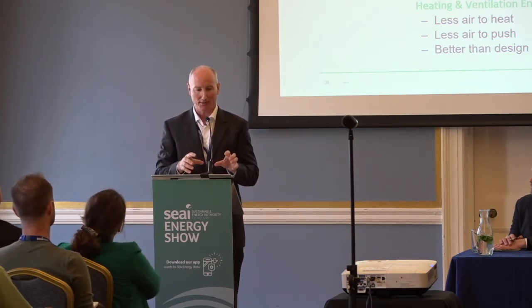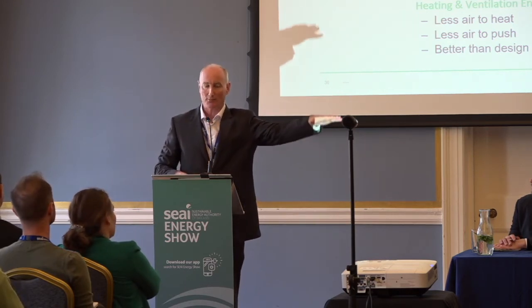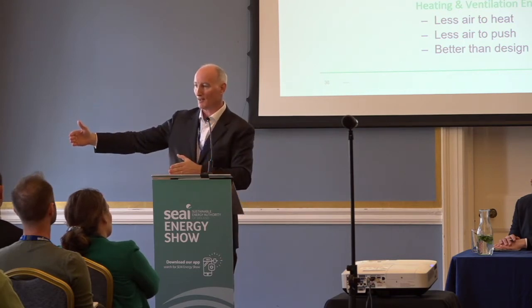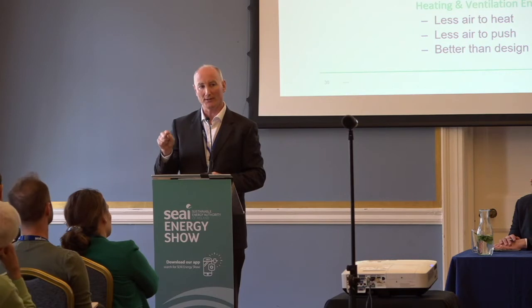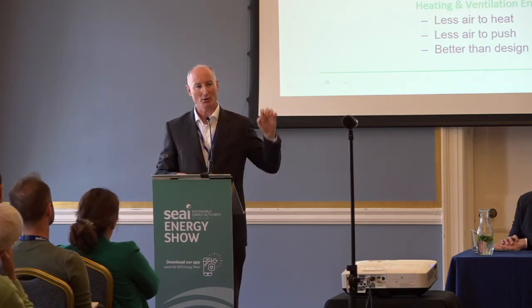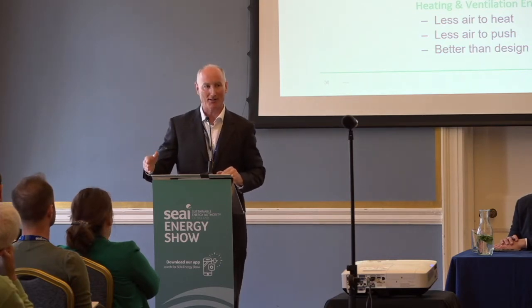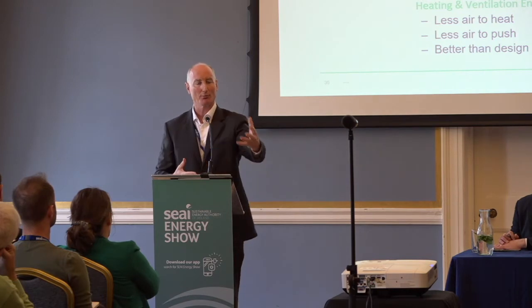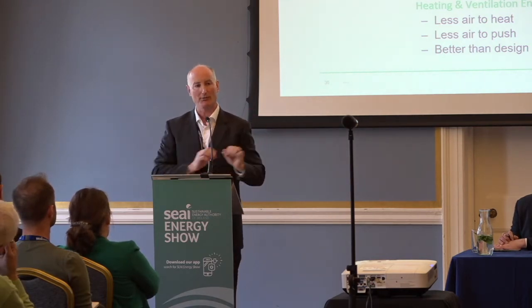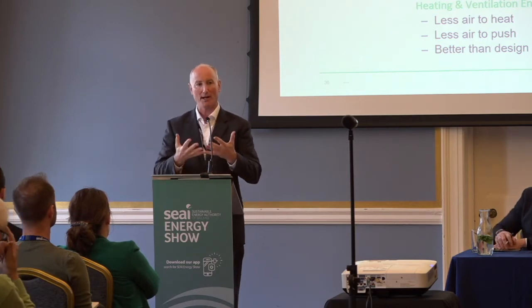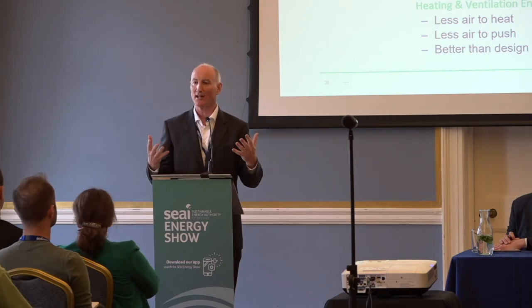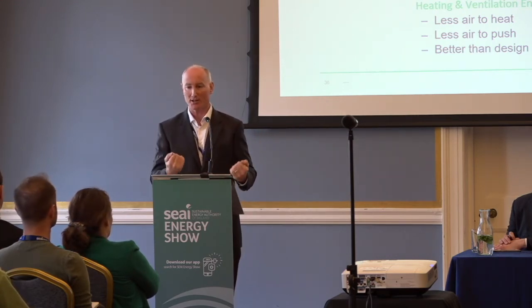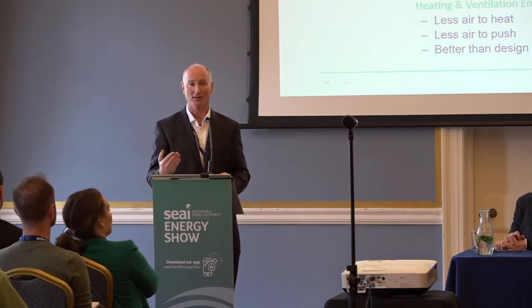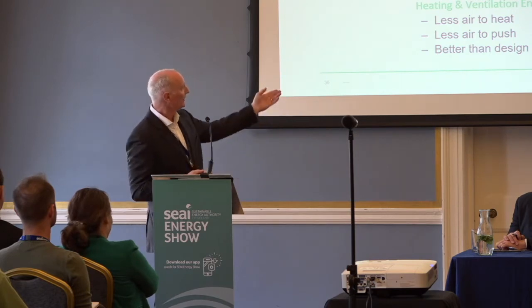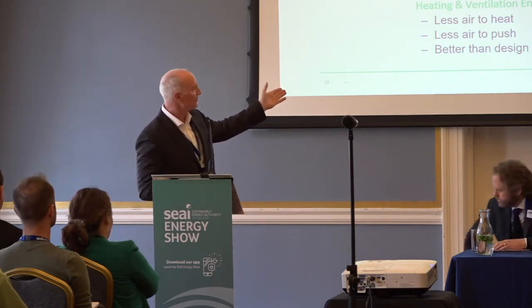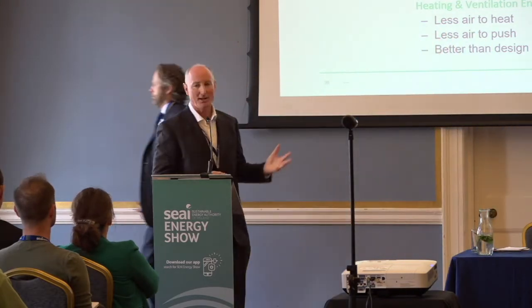What then happens is the office air supply can be turned down automatically, and the meeting room supply can open up. We can even push in more than the design quantity of air into a space, because you pull from one and push to the other. Even while doing that, in any building there's diversity between spaces where people are. You just track the air, follow the people, follow the air. When that microclimate is working, it brings back macro savings from the central plant. The central plant can back off, coming up and down to meet particular requirements, but by and large it's backed off significantly while delivering better than design IAQ. So you get less air to heat and push, less air to cool and push, and better than design IAQ.